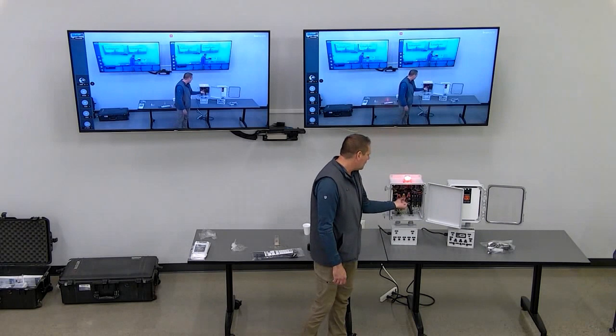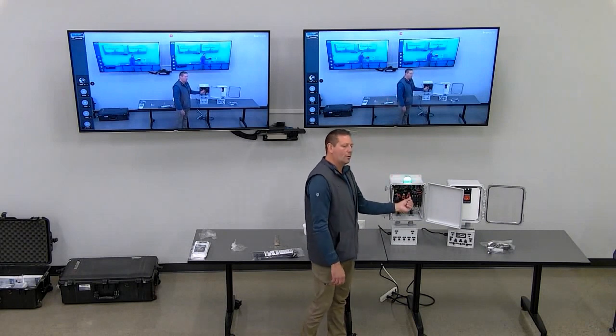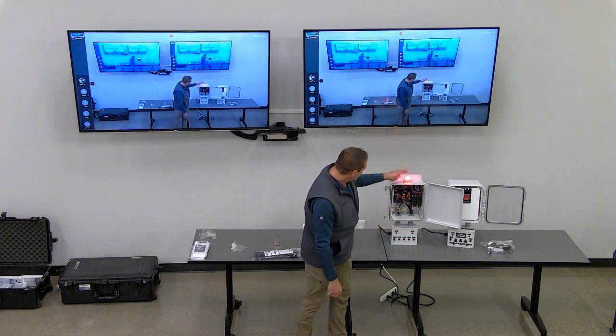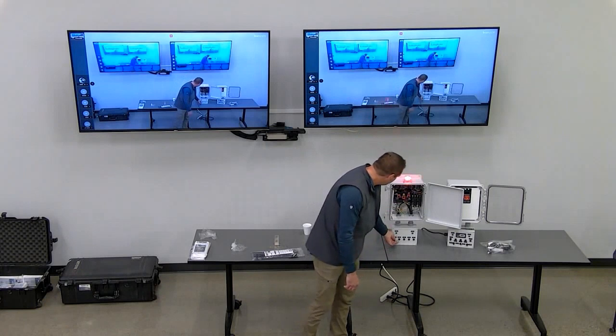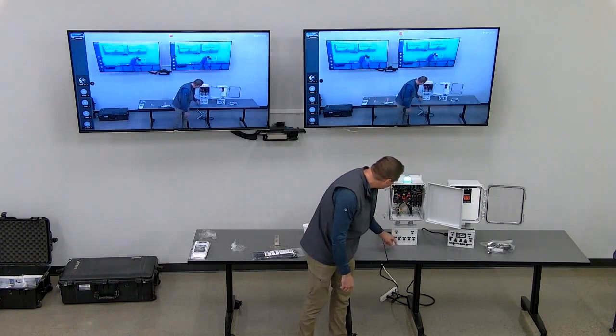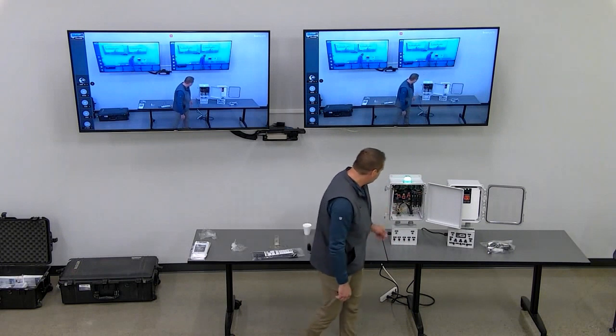And you can adjust this to alternate or always start pump 1 first or always start pump 2 first. And then you have the red indicator. So we have a high level alarm. As it all comes down, they all turn on.